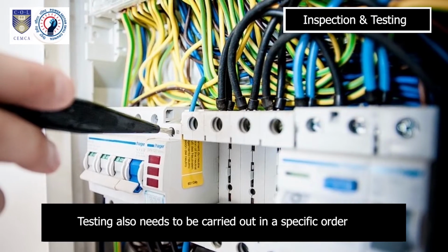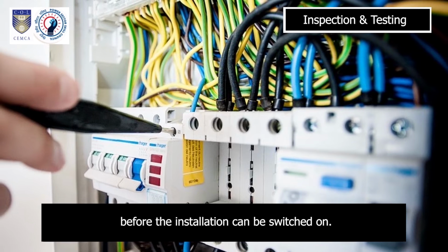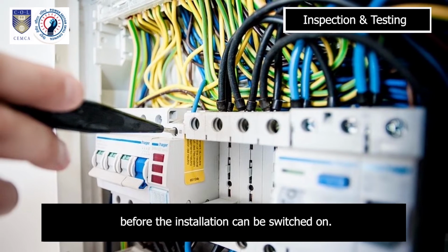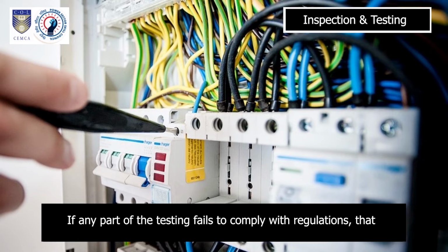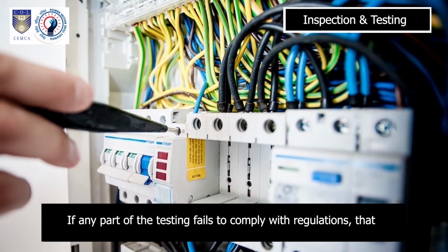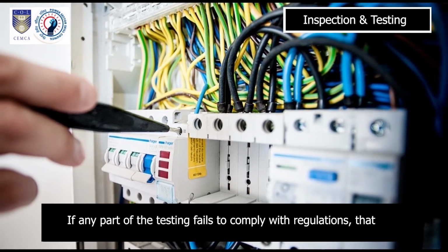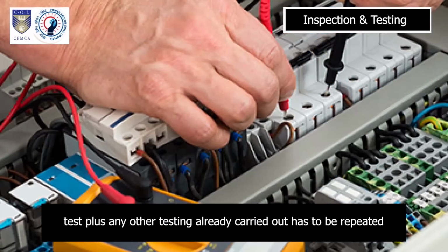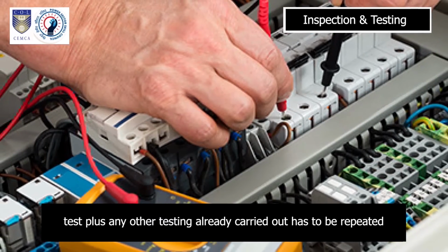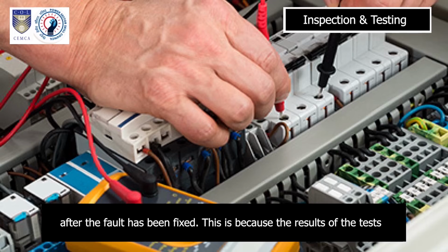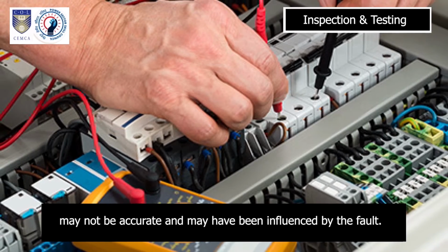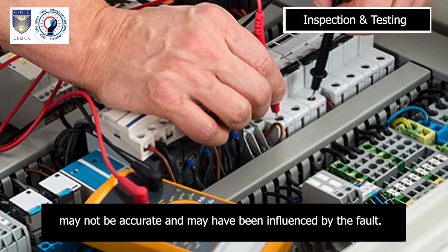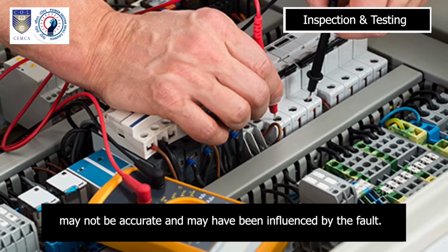Testing also needs to be carried out in a specific order before the installation can be switched on. If any part of the testing fails to comply with regulations, that test plus any other testing already carried out has to be repeated after the fault has been fixed. This is because the results of the tests may not be accurate and may have been influenced by the fault.